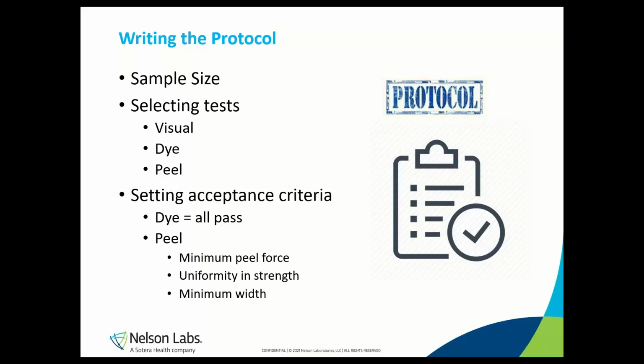Okay, now that we have selected our test methods, we need to set our acceptance criteria. Integrity is the easiest. The seal needs to be continuous without gaps to ensure that no microbes can get through, so we should have a 100% pass rate on the dye test. The peel specification is a bit more tricky. You need acceptance criteria to qualify the sealer, but you don't know what the actual minimum seal strength value for the product will be until much later.